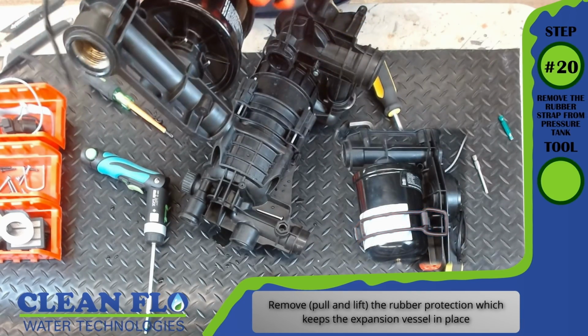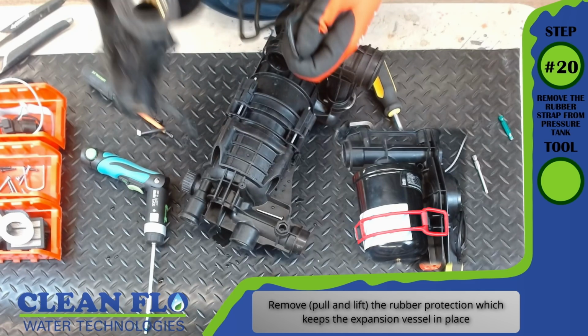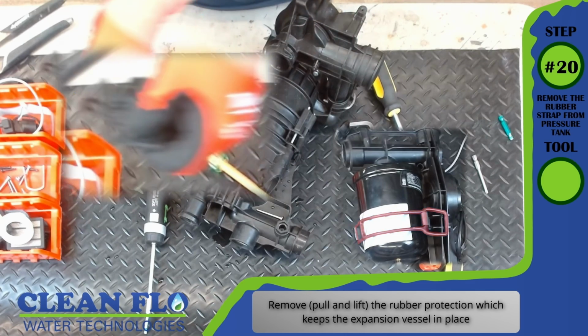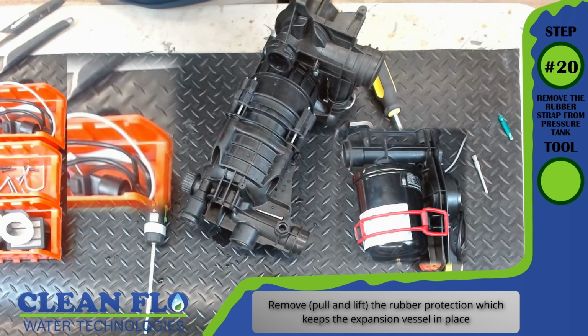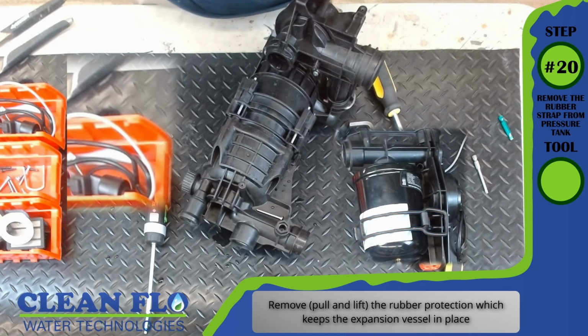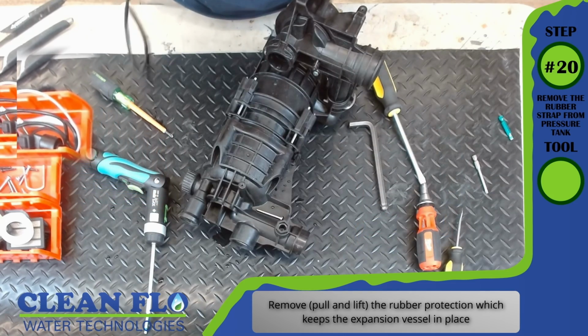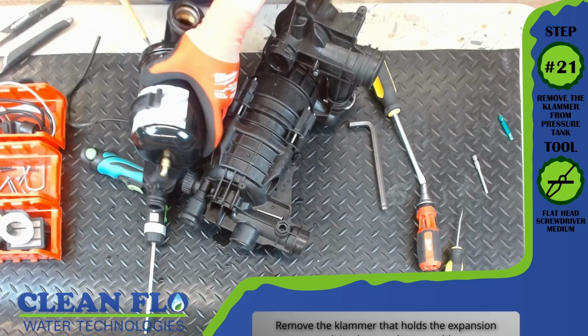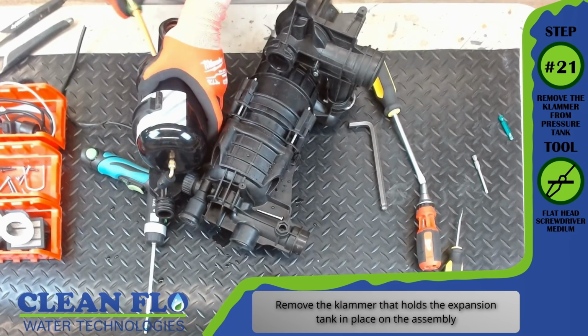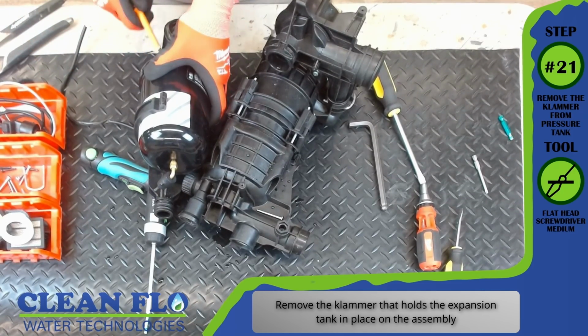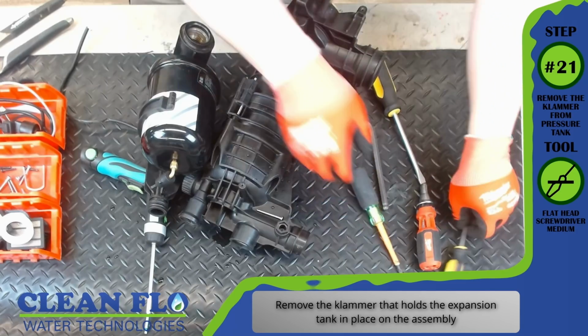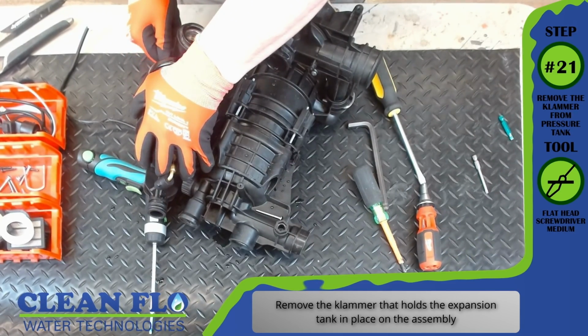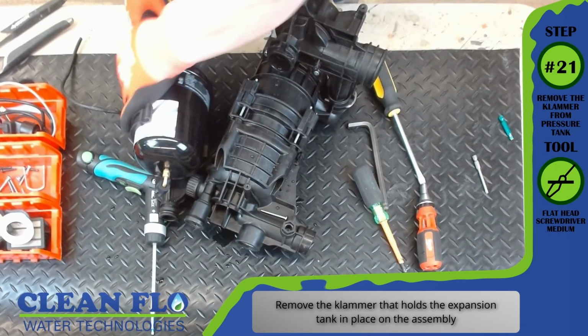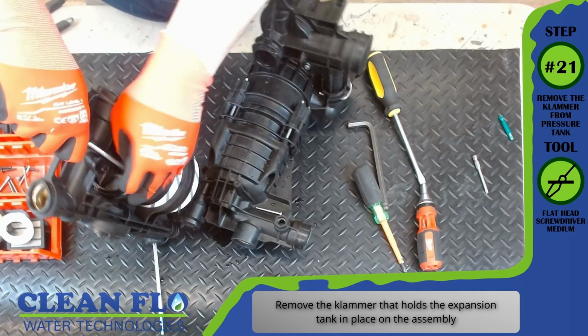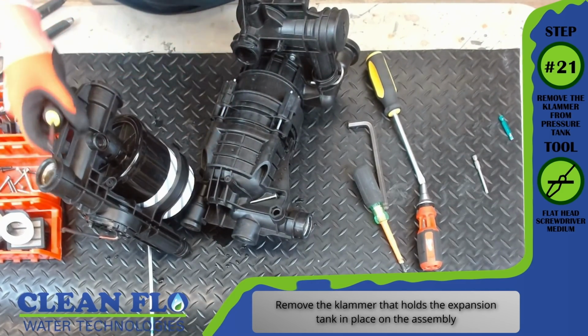Step number 20, remove the rubber strap from the pressure tank. No tool is required. Remove, pull and lift the rubber protection which keeps the expansion tank vessel in place. Step number 21, remove the clamp from the pressure tank. Tool, flathead screwdriver, medium. Remove the clamp that holds the expansion tank in place onto the assembly. Place the clamp neatly with the screws.